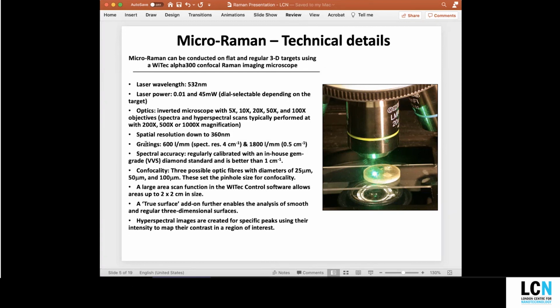Then we have 2 gratings in the spectrometer detector that we can select. One is 600 grooves per millimeter, which gives a spectral resolution of 4 reciprocal centimeters, and 1800 lines per millimeter, which gives a spectral resolution of 0.5 reciprocal centimeter. We have a good spectral accuracy, which is regularly calibrated with an in-house high-grade, gem-grade VVS-type diamond, and that's better than 1 reciprocal centimeter. And I mentioned something about the confocality. We have 3 optic fibers that we can select from: 25 micron diameter, 50 micron diameter, or 100 micron diameter.